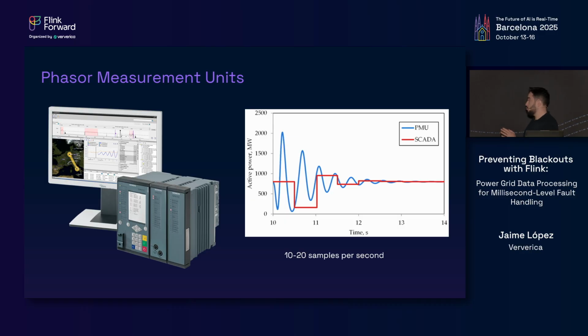They're going to give you 10 to 20 samples per second, so 10 to 20 hertz, which means that in reality what you see in the PMU is the blue wave, while what the SCADA sees is a much lower resolution signal, the red wave. That means that you lose responsiveness, you cannot act before your SCADA pulses again, and you also lose info. You're never going to see this voltage peak in a SCADA, but you will see it in a PMU.